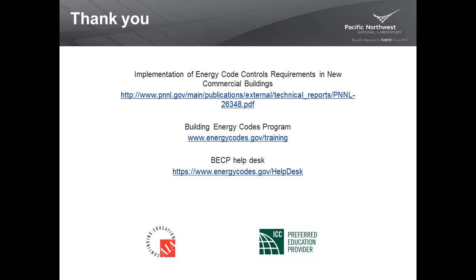And also to note that both of the two model codes have gone to a change. No longer does it say controls need to be capable of anywhere. It actually says capable and configured too. Both 90.1-2016, and I don't remember if it's in the 2015 IECC or was approved for the 2018. But it really makes it much clearer now that configuration, at least at the time of the building being turned over to the owner and getting a certificate of occupancy, is important.